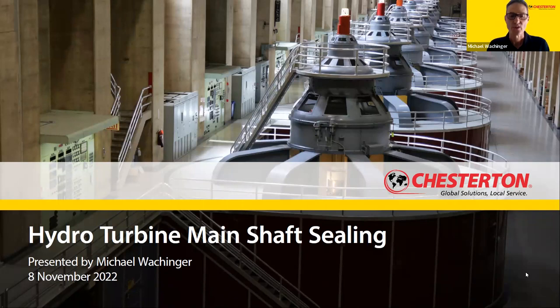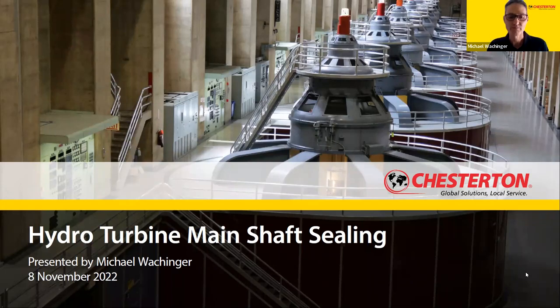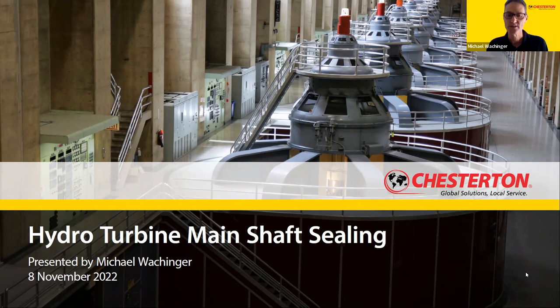Since the very first hydro turbine was designed and installed, sealing the main shaft has been a significant challenge for turbine designers and operators. Making sure the seal is maintained also causes ongoing maintenance headaches for hydropower plant personnel. Teams need to consider issues such as plant acceptable leakage rates, component wear and corrosion, cost of cooling water filtration, treatment of leakage water into the turbine pit, and ease of operation and maintenance.